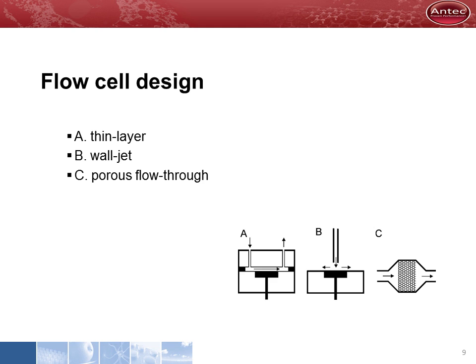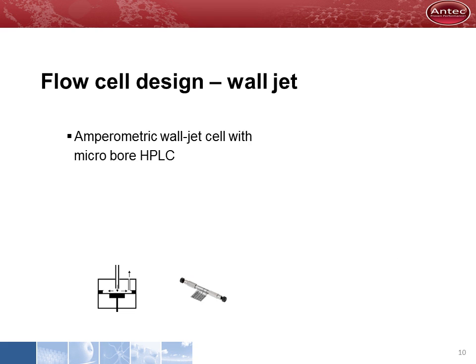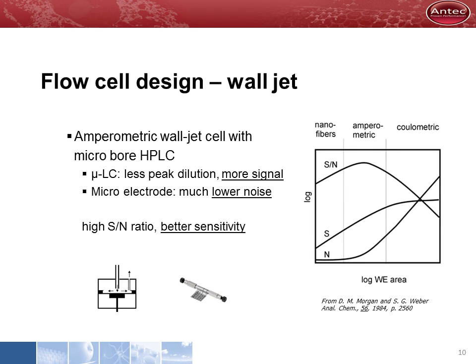Our cells are amperometric cells in contrast to the porous flow-through cells which are called coulometric. Amperometric cells have a huge advantage in that they can be combined with micro-LC without losing performance. Micro-bore LC has less peak dilution and thus more signal. Our amperometric cells have a small electrode area and thus less noise. This results in a better signal to noise ratio, as confirmed by literature publications.